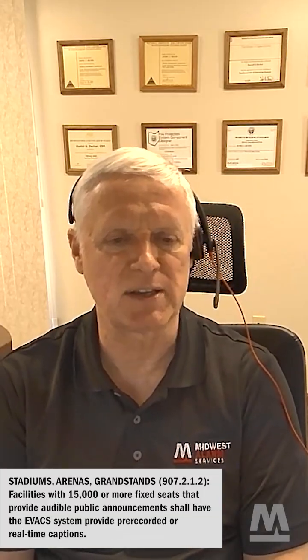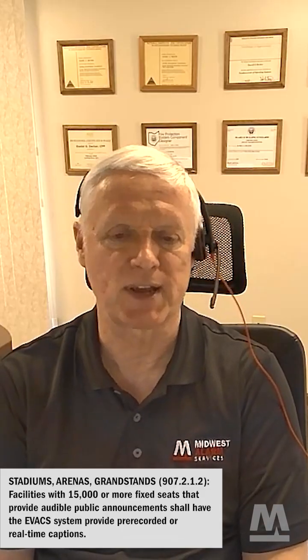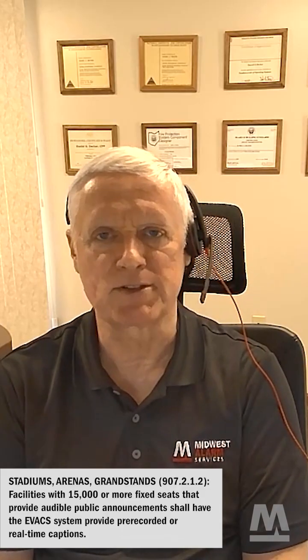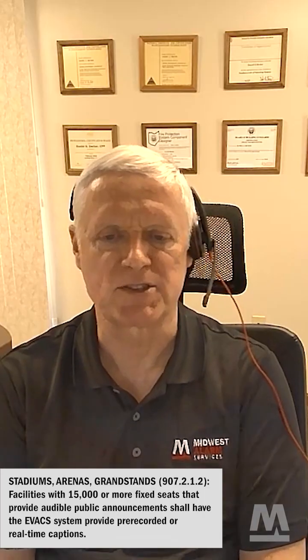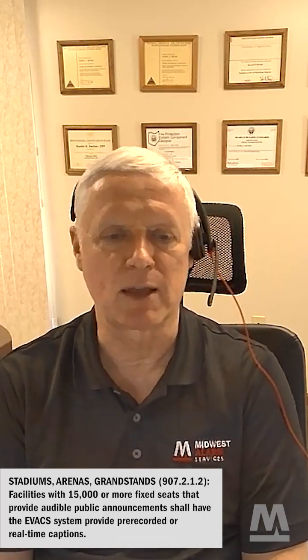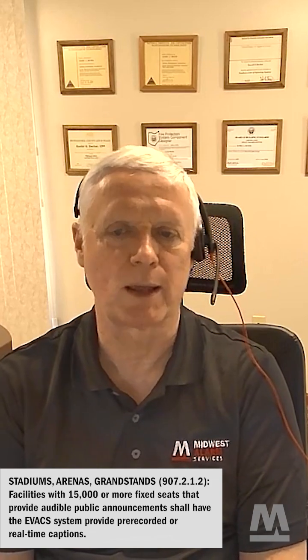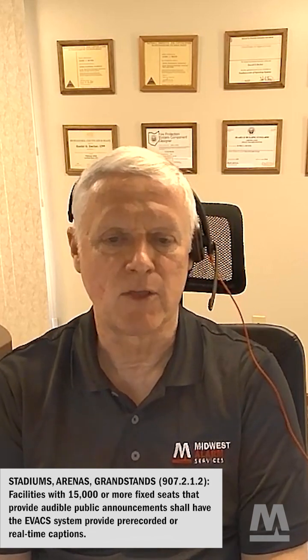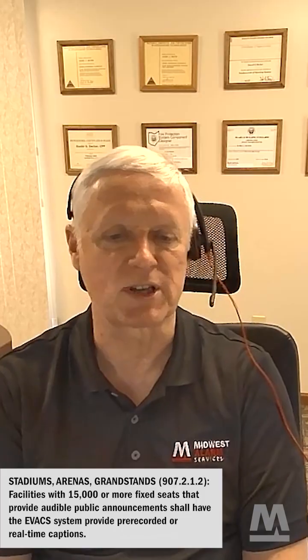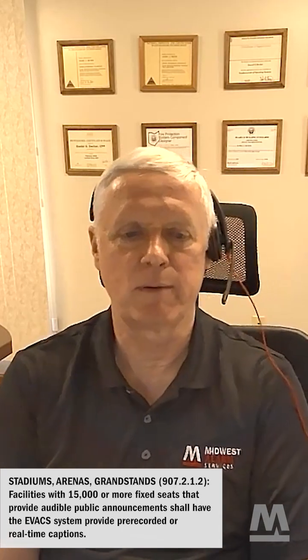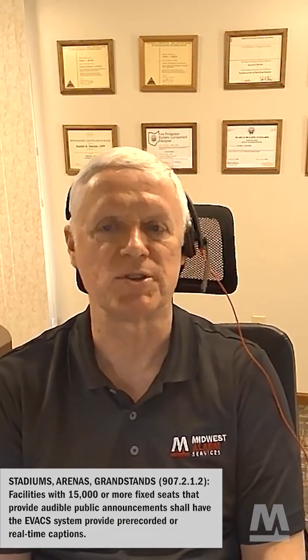The last thing we've got under A occupancies is stadiums, arenas, and grandstands. If you've got a grandstand with 15,000 or more fixed seats and it provides audible public announcements and they have the scrolling notification, then the fire alarm system also has to provide either pre-recorded or real-time captions that go across either the screen. Sometimes they've got a scrolling banner around the stadium's seating, but if that's provided, then the fire alarm has to be integrated in with that.